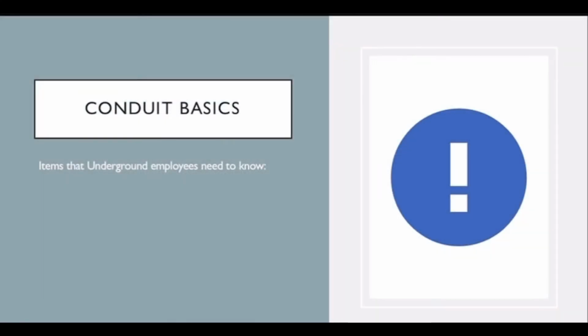Here are the basic things needed to know in order to install conduit. Firstly, employees need to know the type of material that's going to be installed. As mentioned prior, this can be PVC conduit, which is most common for underground, Schedule 40 or Schedule 80, rigid metal conduit, or HDPE, commonly called rolled pipe. All of the above are determined by size required. 2 and 3 inches are most common. Underground crews will also need to know the required conduit depth. TxDOT standard specification calls for an 18-inch minimum cover over the top of conduit to final grade.